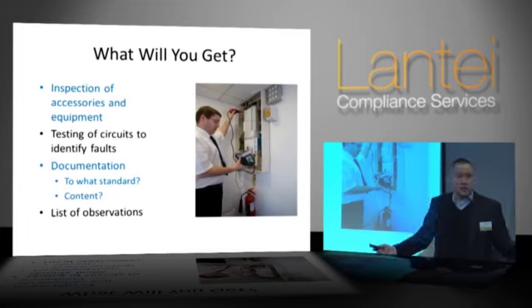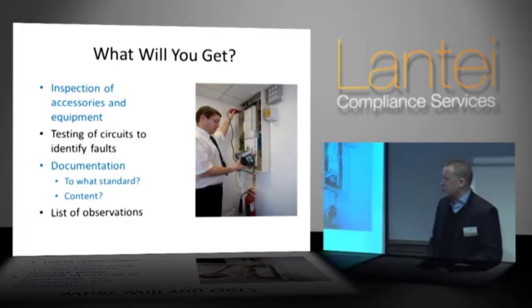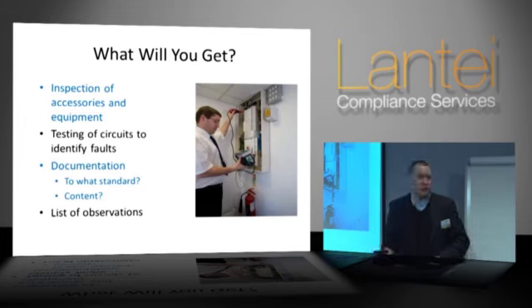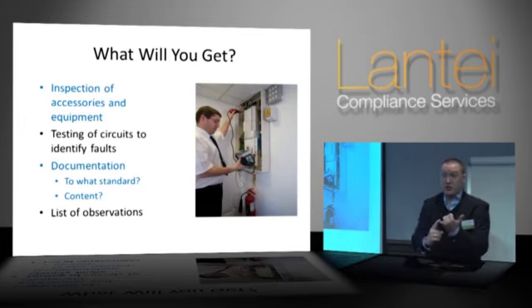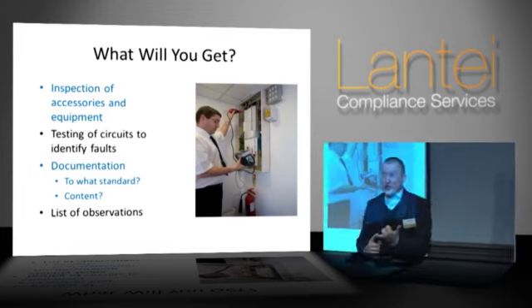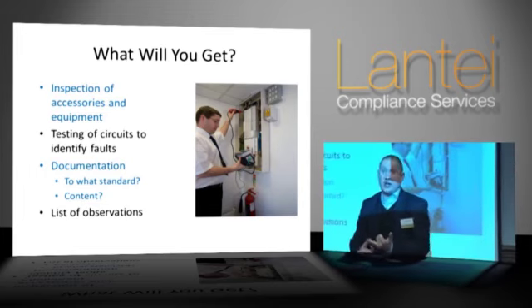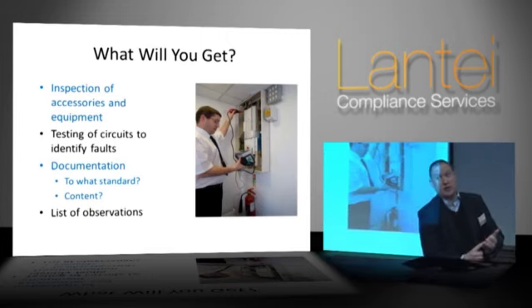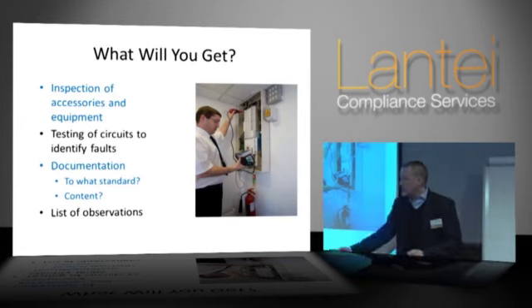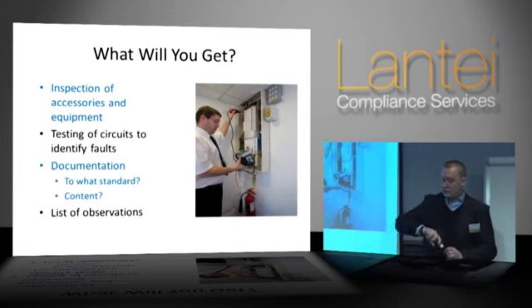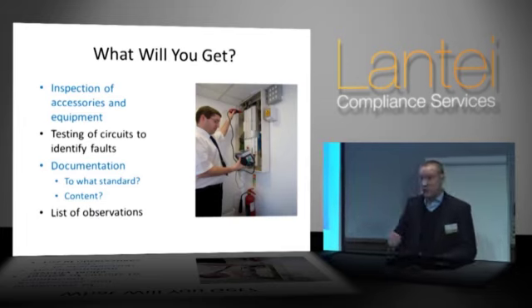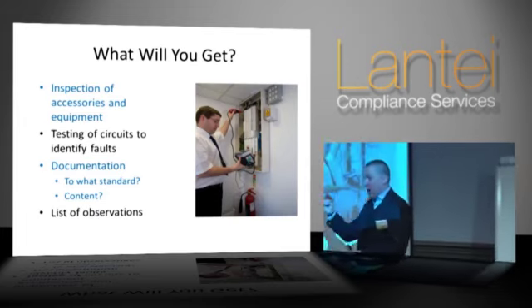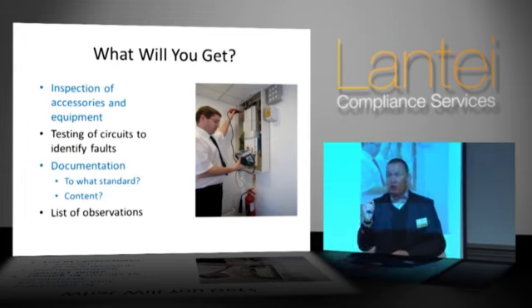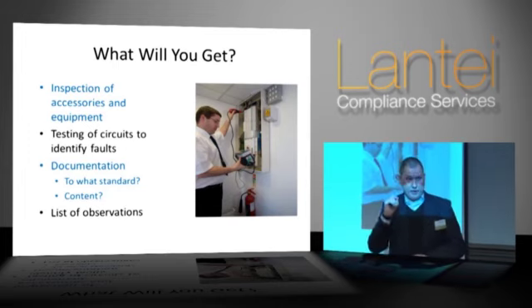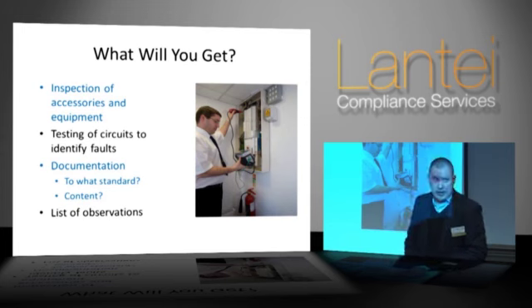What should you be getting? Well, we said a minute ago you should be looking for an EICR, Electrical Installation Condition Report, and it should have a schedule of inspection, i.e. what are the results of the inspection and what inspection was carried out. It should have a schedule of testing that was carried out for each and every board and what the results of that testing are. And most importantly, it should have a list of observations. The reason it needs a list of observations is because these are the items identified as requiring rectification for you to maintain this electrical system, okay?